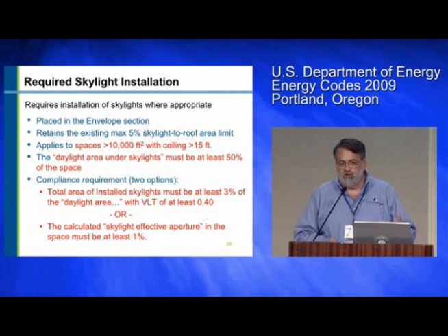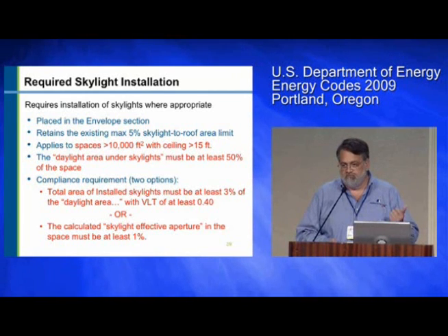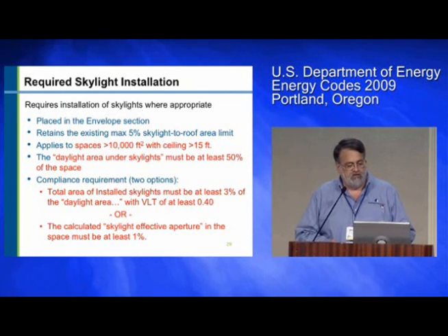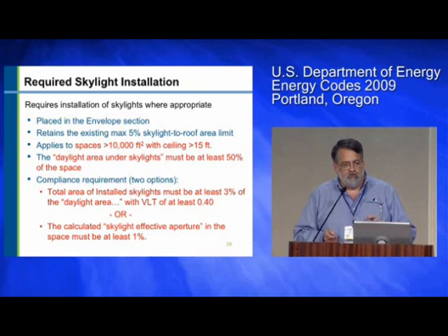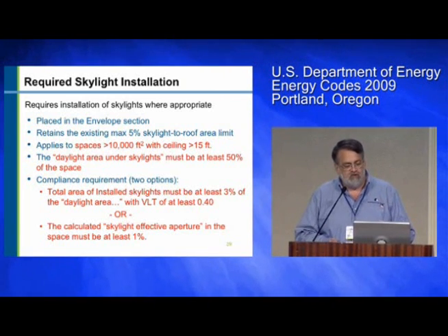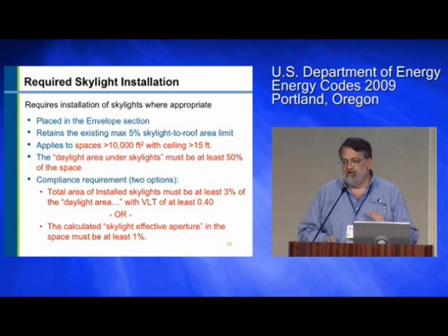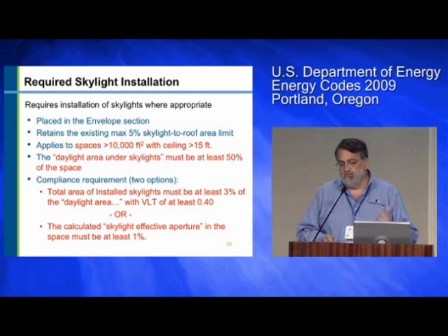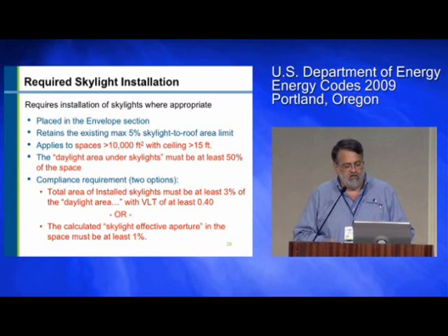It only applies to very large spaces, greater than 10,000 square feet, with ceilings higher than 15 feet. And the requirement is that the daylight area under skylights, which we just looked at the definition of, must be at least 50% of that space. That allows you to exempt some spaces where perhaps daylight is just not an appropriate activity or not an appropriate application. You can apply this in 2 different ways.